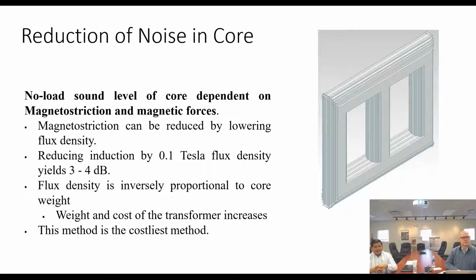No load sound level mainly depends on the magnetostriction and magnetic forces. The magnitude of magnetostriction could be reduced by lowering the flux density. It's the easiest way of reducing the transformer noise. Studies show that reducing the flux density by 0.1 Tesla can reduce the sound by 3 to 4 dB. However, the flux density is inversely proportional to the core weight. So by reducing the flux density, we need to use more core, and that will affect the size of the transformer and the cost, because the core size is bigger, the transformer size is bigger, and that will increase the transformer cost. So if customers really want a lower sounding transformer, then they probably might have to pay a little more to get that. Yes, sir. Okay.